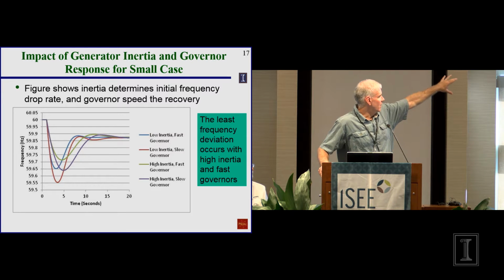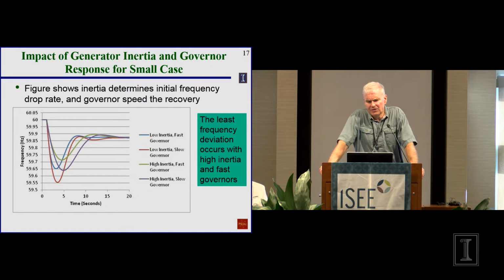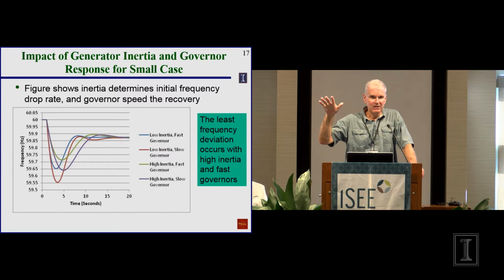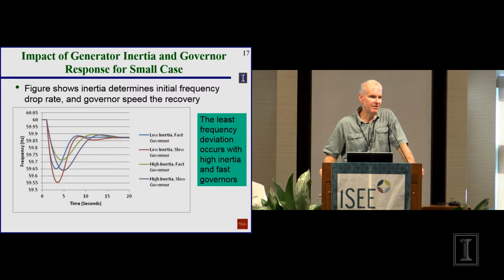The one that goes the lowest, 59.55 hertz, is a grid with slow responding generators without much inertia. One issue with fuel source free generation, like PV where the sun is free, is you try to operate that generator at its maximum output. If you have PV on your roof, you want to get as much out of it as you can, but that means there's no reserve associated with that generation. Similarly, if you operate a wind turbine, you're trying to capture as much energy from the wind as you can, and that's good, except there's no reserve associated with it. So if we lose other generation, somebody has to make up the difference, and if it's not wind and solar PV, it's got to be nuclear reactors, coal, or natural gas.